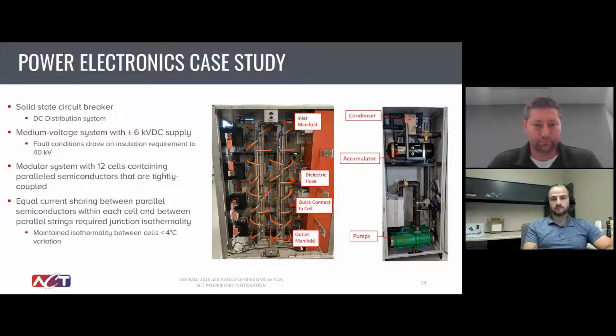similar to what Brian was showing on the previous slide for the CDU of the data center application. This was a CDU for this particular power electronics application. In the back, in the picture on the left, we're showing the manifold distributing the liquid and collecting the vapor from each of those cells. Again, we're using those orange hoses you saw on some other slides. So this was able to stand off the 40 kV of required voltage between parallel sides of the system. Any one of those cells needed to stand off up to 40 kilovolts of isolation in a fault condition.